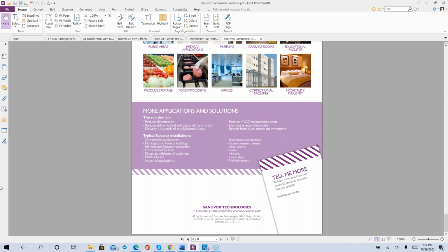The reason for that long lead time is that there are dozens of UV light manufacturers, Sanuvox among them, American Ultraviolet, et cetera, et cetera. There are dozens of those manufacturers, but there are really only 4 or 5 UV bulb manufacturers. And when COVID first came in, they had about a 50% absentee rate, and they lost a lot of their production. Once they geared back up, they are running 3 shifts a day for 6 days out of the week, and they are still not able to catch up. So that's part of the reason why there is such a long lead time on that.